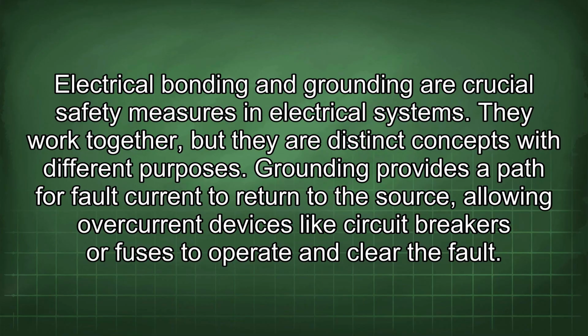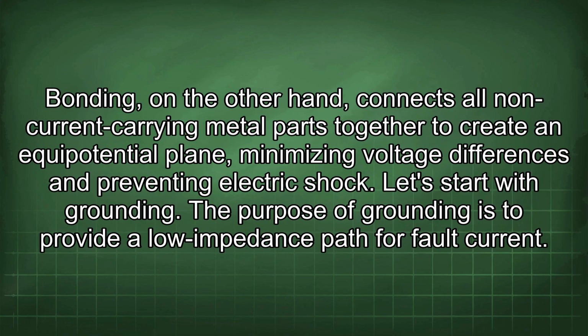Electrical bonding and grounding are crucial safety measures in electrical systems. They work together, but they are distinct concepts with different purposes. Grounding provides a path for fault current to return to the source, allowing overcurrent devices like circuit breakers or fuses to operate and clear the fault. Bonding, on the other hand, connects all non-current-carrying metal parts together to create an equipotential plane, minimizing voltage differences and preventing electric shock. Let's start with grounding.